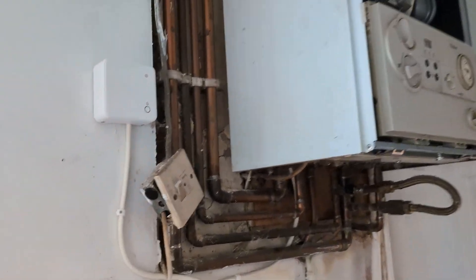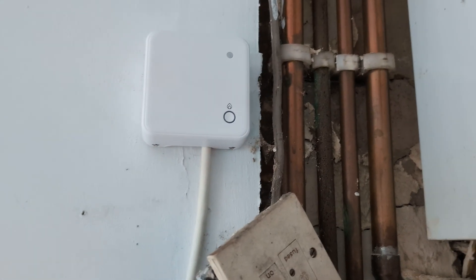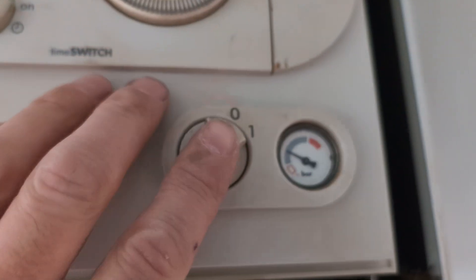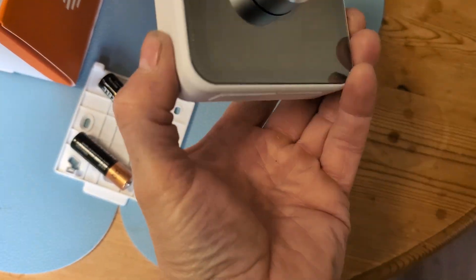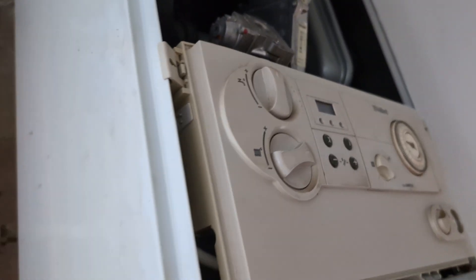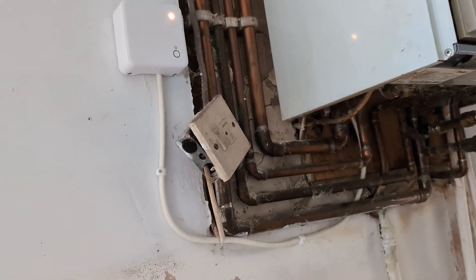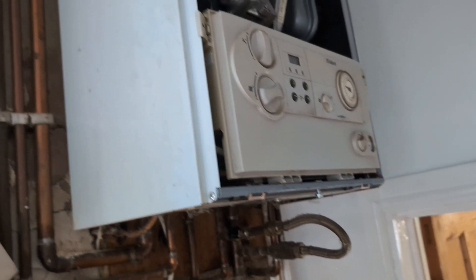How to get your Hive thermostat working after you've installed it. Make sure you've wired the receiver correctly, then turn on the power. Don't turn on the boiler yet, and no batteries in the thermostat. All we're testing firstly is the receiver. So the power's turned on and we've got an amber light flashing on the receiver, which is correct.